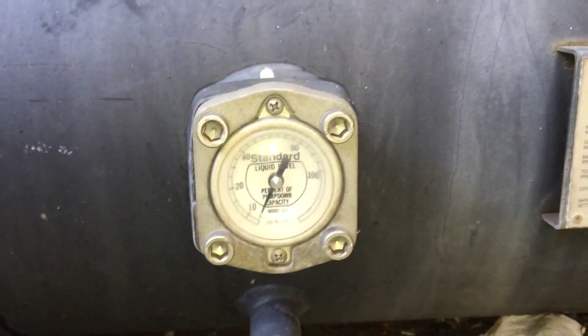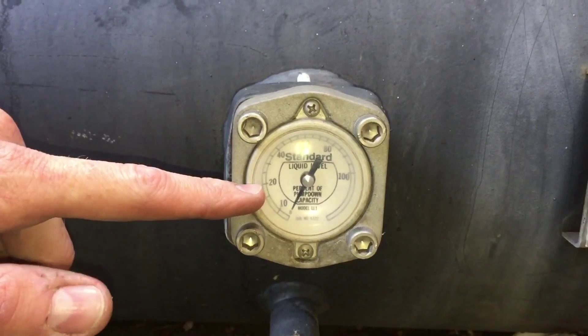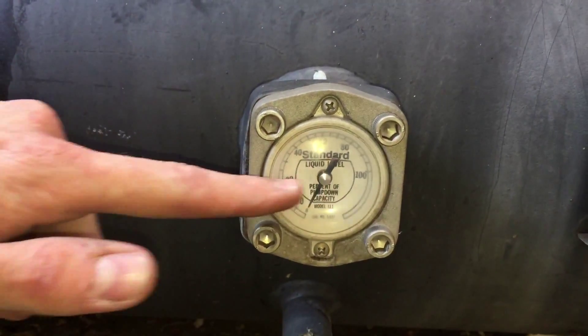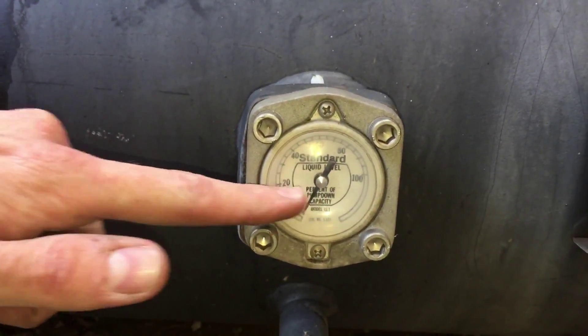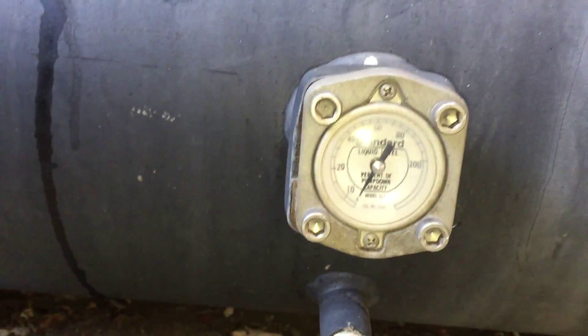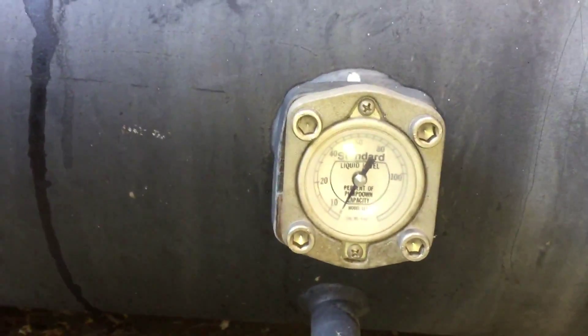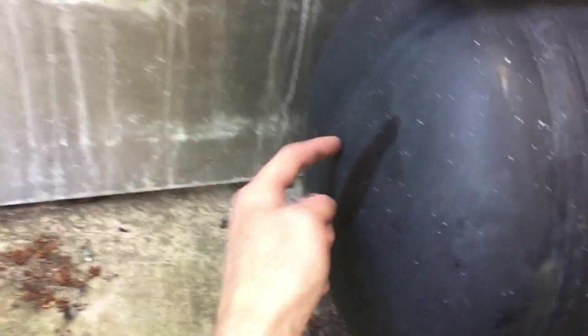Just speaking to my friend on the phone — a good engineer — he said that you're looking for about 15 to 20% as a nice level for the liquid level. And I guess that's on any kind of liquid levels, but this one actually tells you the percentage. Because sometimes on these you can have sight glasses full of oil, so obviously you want to see — there's usually two, one at the bottom and usually one halfway — definitely want to see the bottom one at least full.